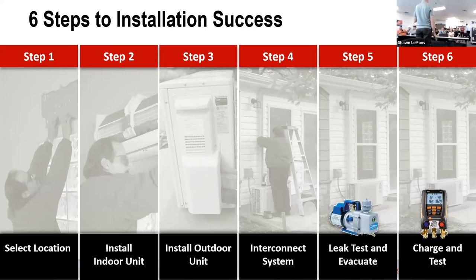It's the leak testing, pressure testing, and then the charge. These systems depend on managing temperature and pressure of the refrigerant, so we have to make sure it can handle up to 600 PSI, roughly twice what you'd see in a typical air conditioning system. Folks used to working on air conditioners have to change their mindset and their equipment to handle 600 PSI positive pressure tests, as well as triple evacuation. It's just a different routine, with extra steps and extra details involved.